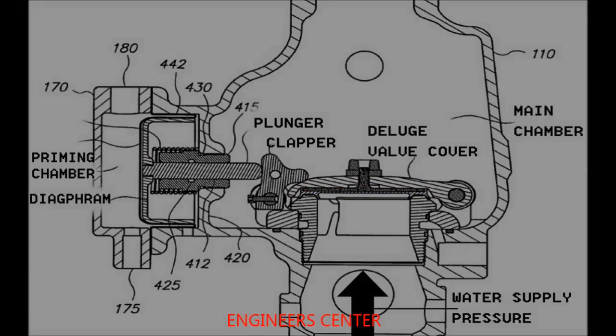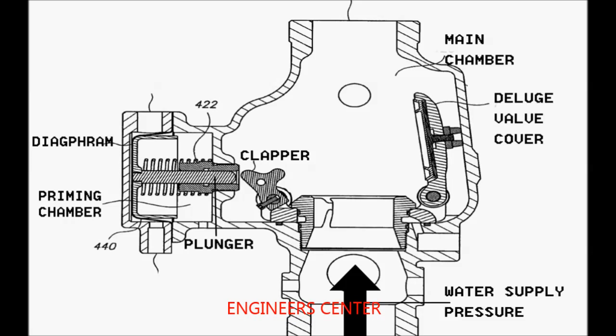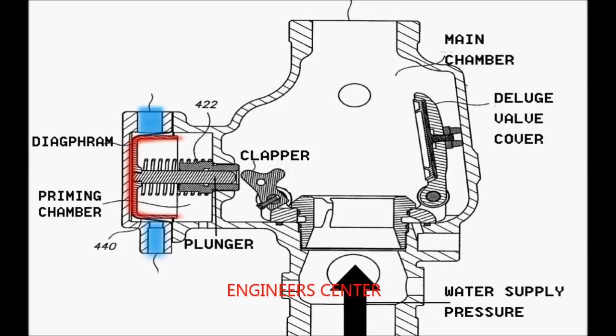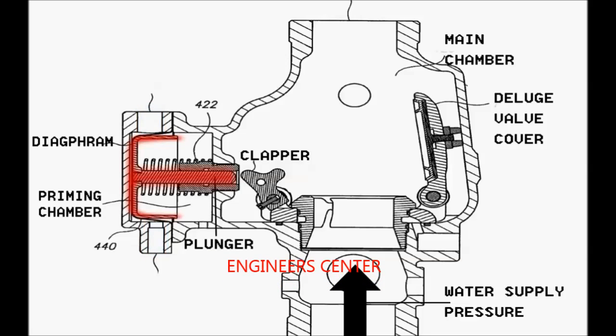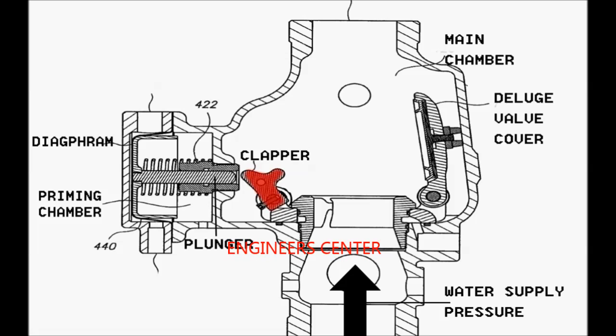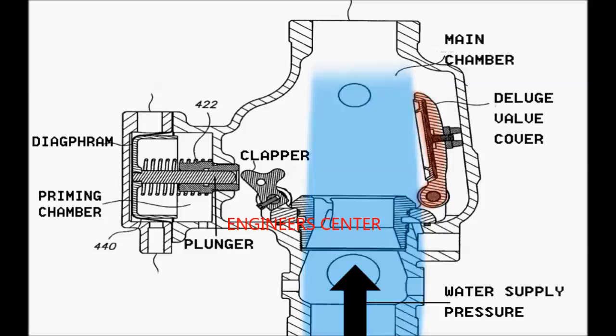The priming water pressure behind the diaphragm is balancing the water supply pressure, causing the deluge valve to be closed. The release of the priming water pressure behind the diaphragm causes the diaphragm together with the plunger to move backwards, removing the pressure on the clapper and consequently opening the deluge valve by the action of the water supply pressure.